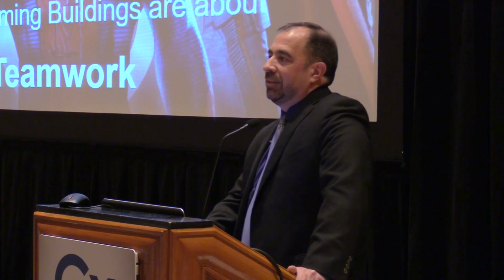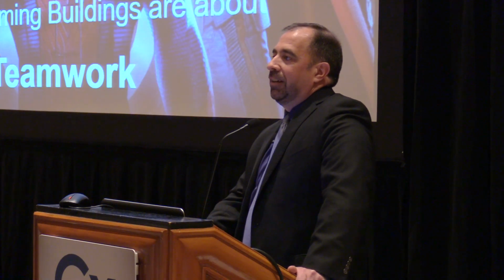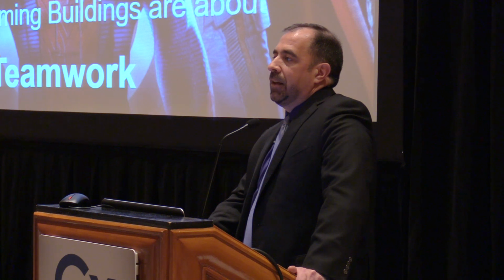Way in the back, question. Just add one thing to your presentation. So, on functional testing, the one thing that we have found a lot, maybe probably 80%, is that the breakers both on the normal side of the transfer switch and the generator are not set for the coordination study.